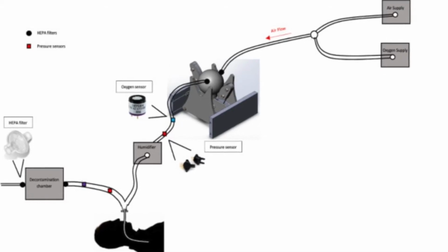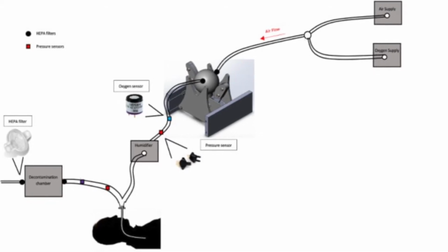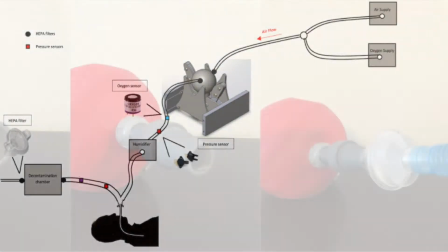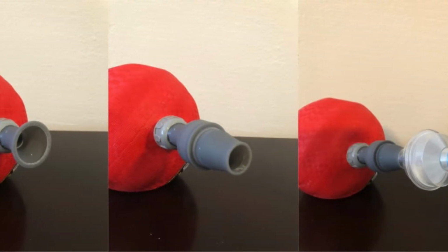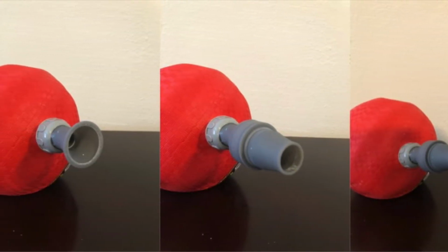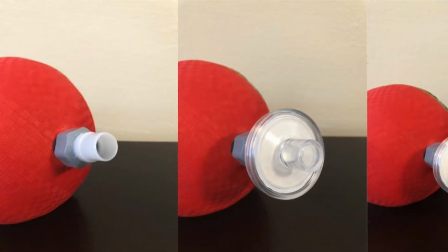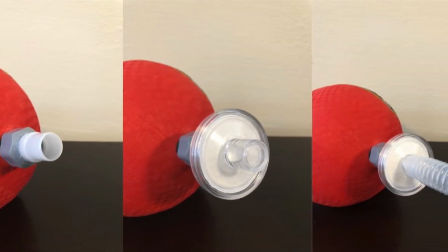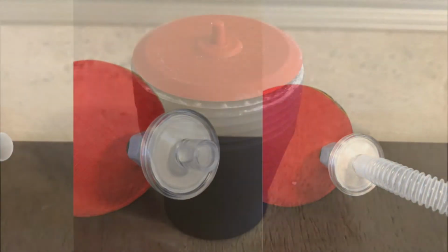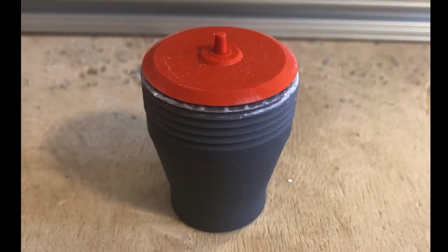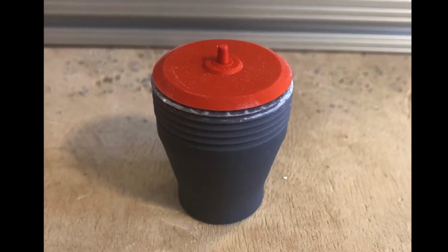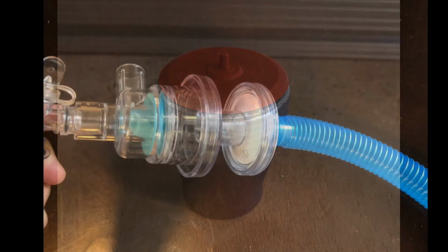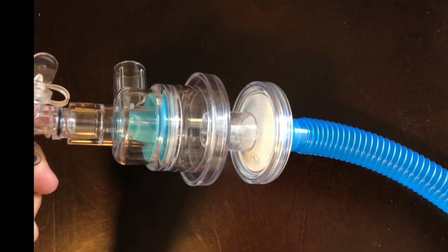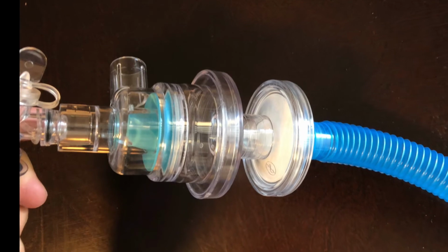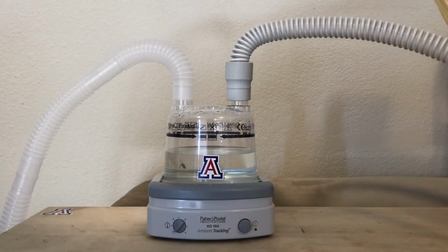The air circulates through the chamber and out to the patient through an external compression. The kickball will provide an inlet and outlet such that airflow tubing can be attached. This provides strong sealing and avoids any air escaping. Therefore, this airtight seal system is strong and long-lasting. We also developed and 3D printed our own check valve and purchased HEPA filters because our concept did not have an ambu bag with built-in air check valves and filters. So this allowed us to provide a steady flow of filtered air to the patient.